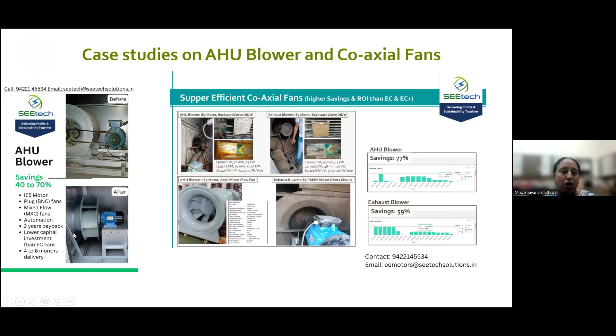Now super efficient coaxial fans have been used, giving higher savings and ROI than EC and EC plus fans. In AHU blower we received savings of 77%, and for exhaust blower the savings were 59%. In AHU blower you can see this is belt driven, while after the change it is direct mount. So these savings are because the losses due to belt drive have been reduced further.